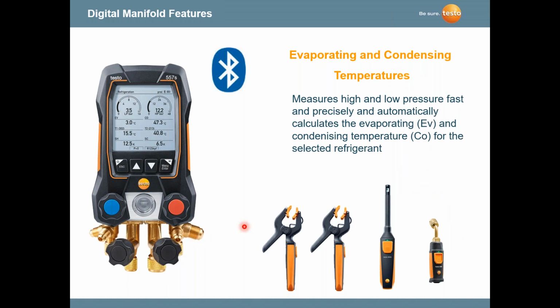Not only are we measuring temperatures, but we're doing the calculation for you from the pressures, the low side pressure and the high side pressure. We're calculating the saturation temperatures. You'll notice on this instrument here, we're not only measuring pressures, but we're giving a reference of an analog gauge digitally, of course. This is a digital readout of an analog gauge here. And in between the gauge itself is the PSI gauge reading, the low side and the high side.